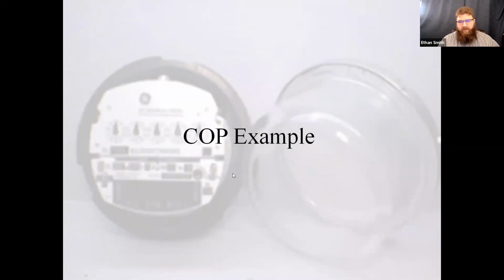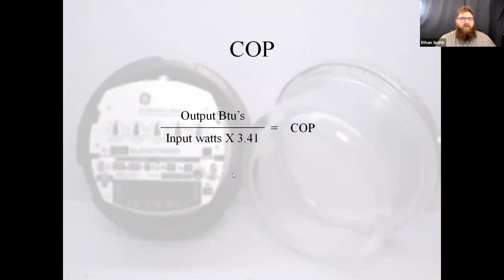Okay, so let's play with COPs for a second. So COP is simply our output BTUs divided by our input wattage times 3.41. So 3.41 is your conversion factor from electrical wattage to BTUs in electric heat. So if you had 1 watt of electric power going into an electric heater, you would get 3.41 BTUs of heat out of that electric heater. And that's just a universal constant.